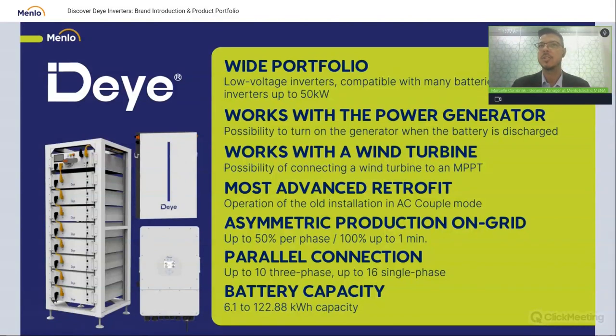It also works well with power generators, and can help you charge and discharge the battery. Please make sure the generator has an automatic stop-start function so it can receive a signal from the inverter to start. Do not use generators that you have to pull-start, because they will not work. It can also work with wind turbines, as I mentioned, on hybrid systems and grid-tied systems.